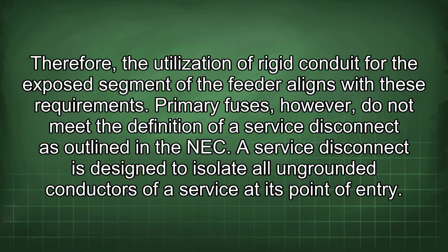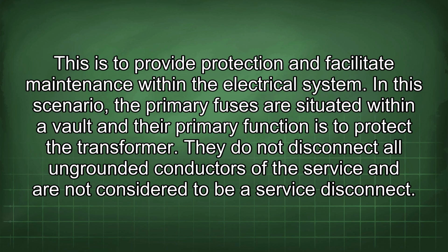Primary fuses, however, do not meet the definition of a service disconnect as outlined in the NEC. A service disconnect is designed to isolate all ungrounded conductors of a service at its point of entry. This is to provide protection and facilitate maintenance within the electrical system. In this scenario, the primary fuses are situated within a vault and their primary function is to protect the transformer. They do not disconnect all ungrounded conductors of the service and are not considered to be a service disconnect.